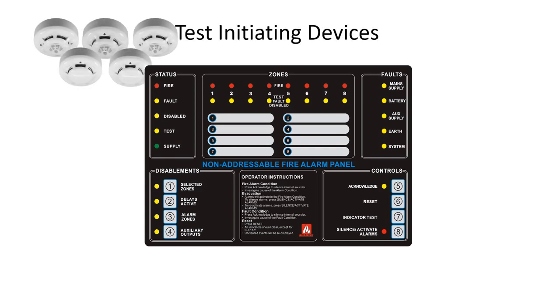To test detectors and other initiating devices, enter Access Level 3. Press the Indicator Test button. The Test LED and the Acknowledge LED will flash. Press the Acknowledge button to confirm. The Acknowledge LED will be off, and the Test and the yellow zone LEDs will be on. Test a device connected to each detection zone.